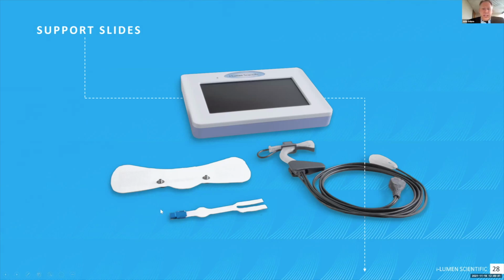Yep. So the electrode kit itself is essentially two electrodes, and that is the disposable kit. The lead wire and earpiece right now are being treated as part of the device and are a maintenance component that we cover for the clinicians, or for the physicians, the practices, going forward.